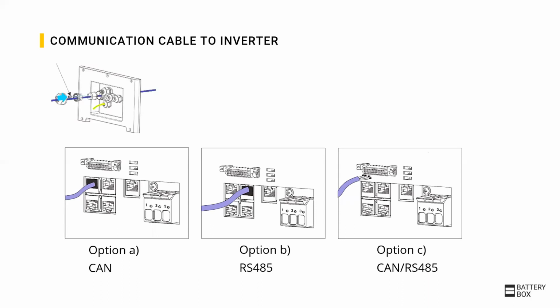For most inverters, you can choose between two connection options. For all inverters, you can use option C and connect the communication cable by pins. Dependent on the inverter, you might also have the option to connect the communication cable by a normal RJ45 head on the inverter cable. Please always refer to the manual to check how the combined inverter has to be connected.